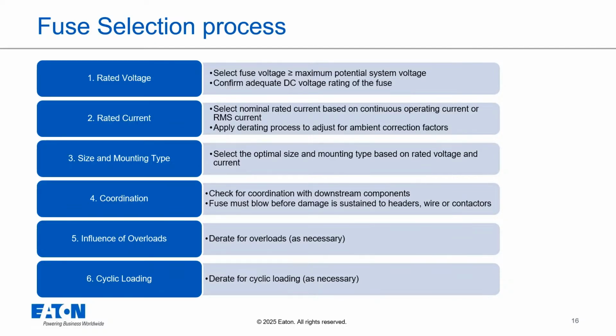Step 4, coordination. You must check that the fuse will blow before other downstream components like connectors, wires, or contactors sustain damage. This is done using time current curves. Step 5, influence of overloads. Here we account for potential overloads or inrush currents that might be present in the load profile. And then finally, step 6, cyclic loading. Here we consider the effects of repetitive variations in current on the fuse element's fatigue and lifespan.